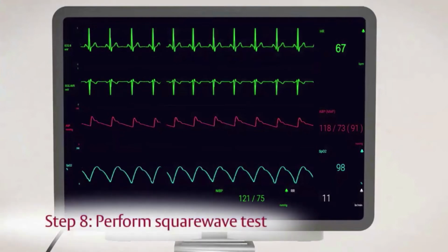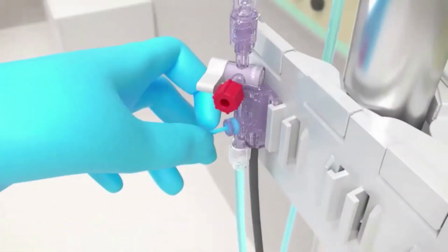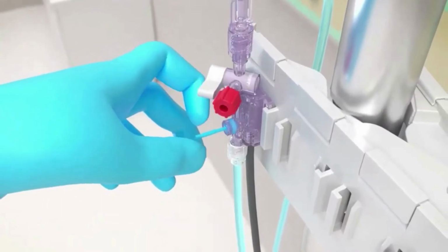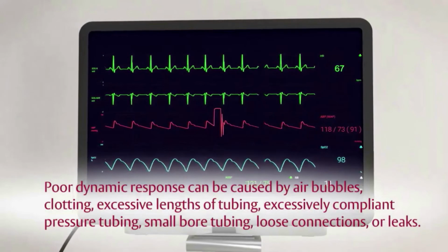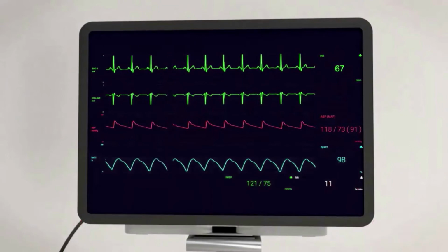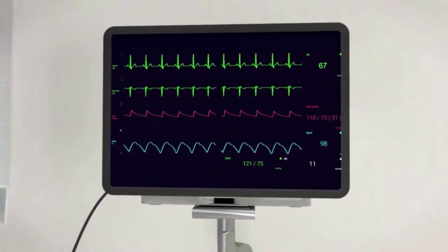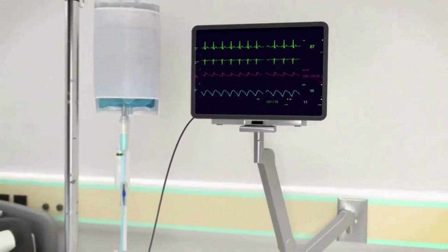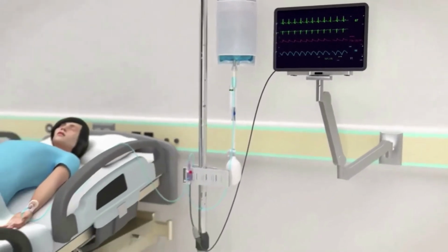Step 8. Perform a square wave test to assess the frequency response of the system by pulling the snap tab and releasing quickly. Please be advised that poor dynamic response can be caused by air bubbles, clotting, excessive lengths of tubing, excessively compliant pressure tubing, small bore tubing, loose connections, or leaks. Confirm the pressure channel has the appropriate label, scale, alarm settings, and color coding for physiologic pressure being measured. The calibration procedure is now complete.